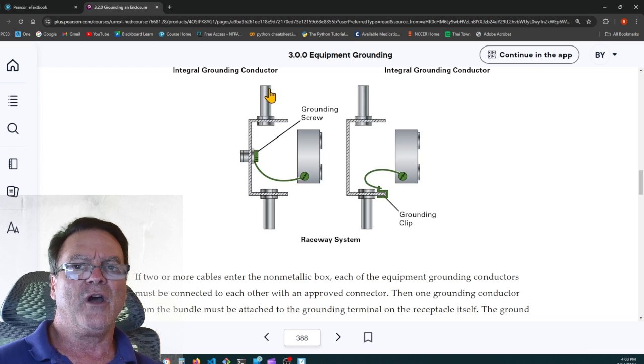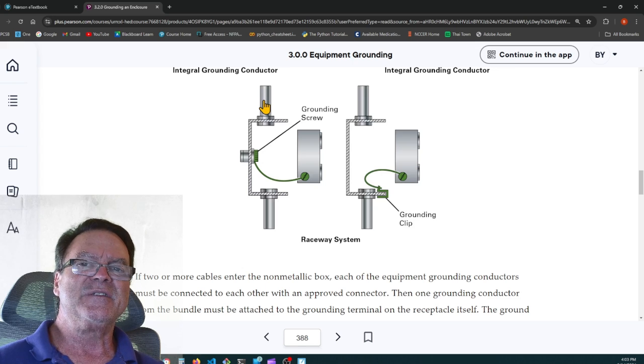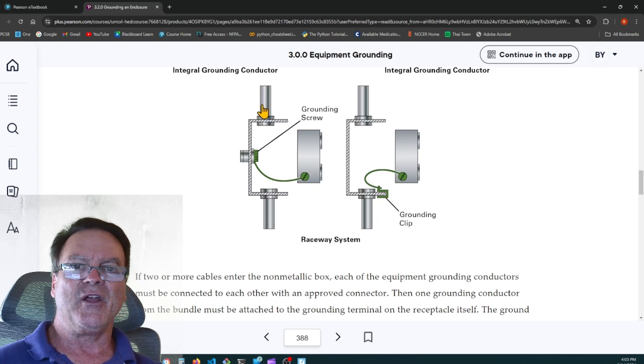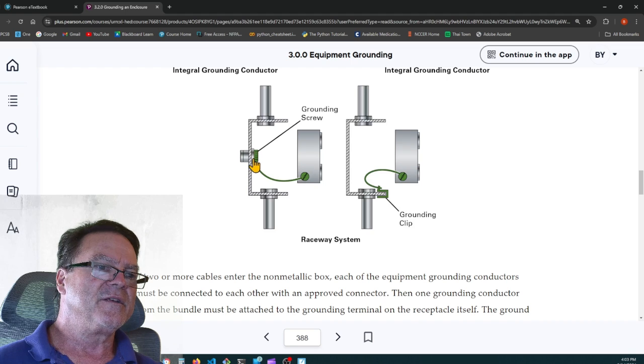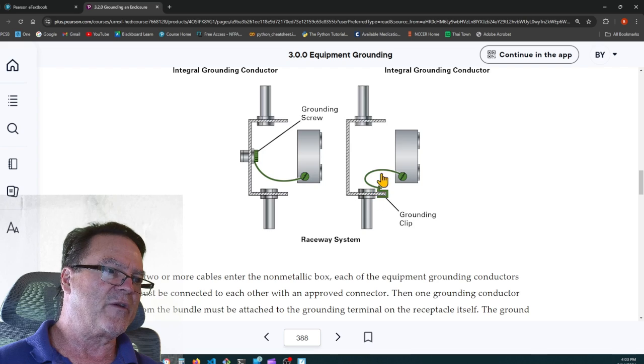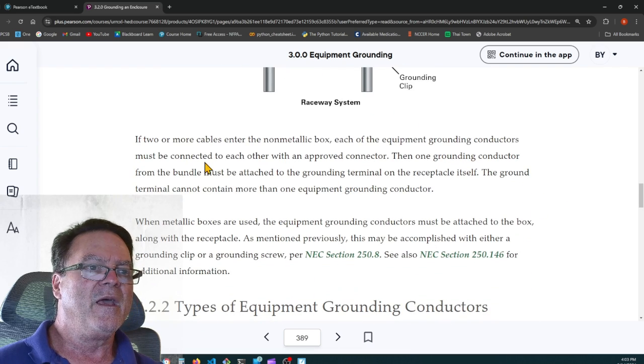You have to check local codes because the National Electrical Code says we can use EMT, rigid conduit, and intermediate conduit as an equipment ground, but some local municipalities will say no. So be very careful about just grounding the receptacle, the green screw, to the back of the box. That's using the raceway back to the panel as the equipment grounding conductor.